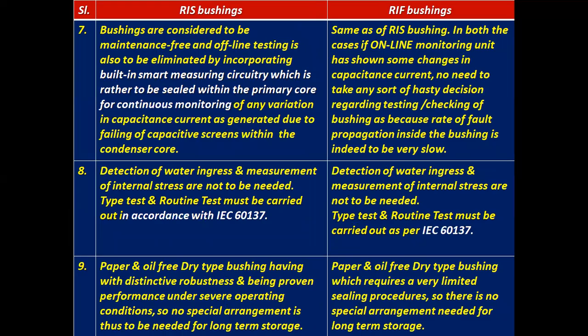Number 7, for RIS bushings, bushings are considered to be maintenance free and offline testing is eliminated by incorporating built-in smart measuring circuitry, sealed within the primary core for continuous monitoring of any variation in capacitance current as generated due to failing of capacitive screens within the condenser core.